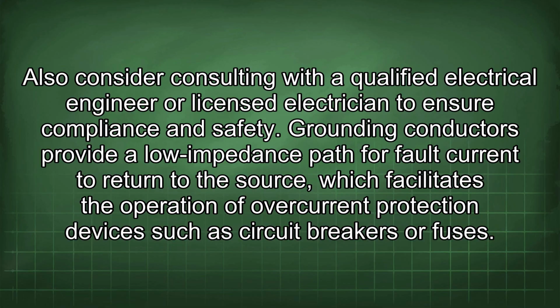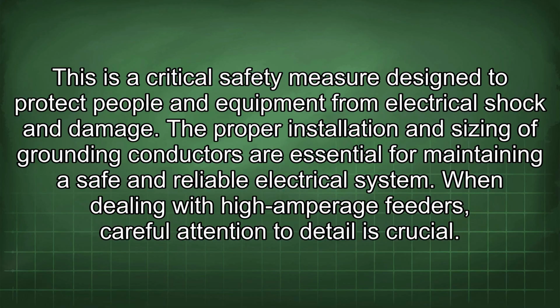Grounding conductors provide a low impedance path for fault current to return to the source, which facilitates the operation of overcurrent protection devices such as circuit breakers or fuses. This is a critical safety measure designed to protect people and equipment from electrical shock and damage. The proper installation and sizing of grounding conductors are essential for maintaining a safe and reliable electrical system.